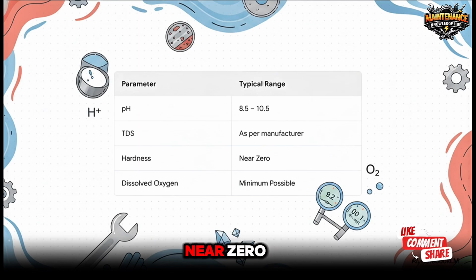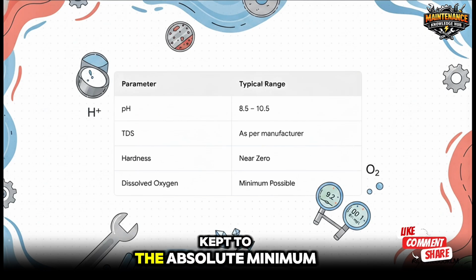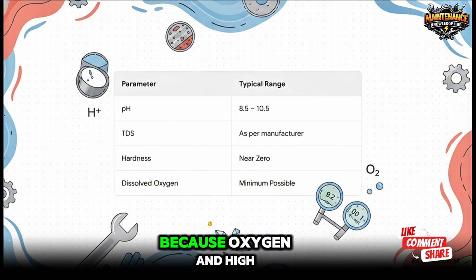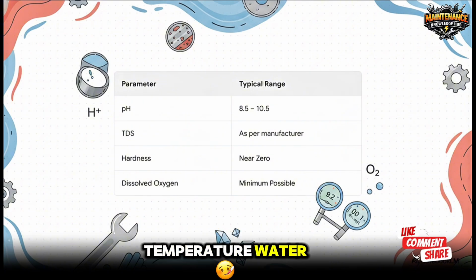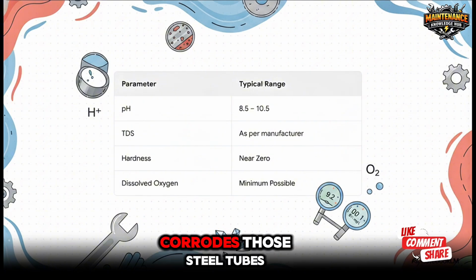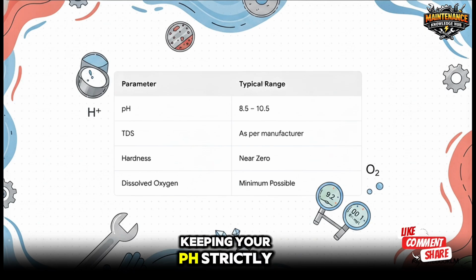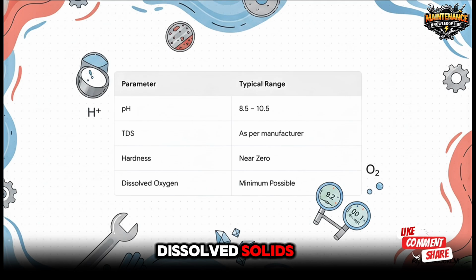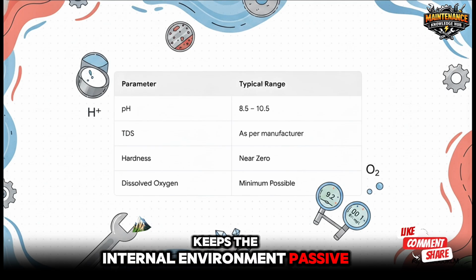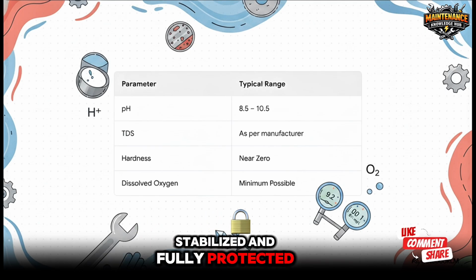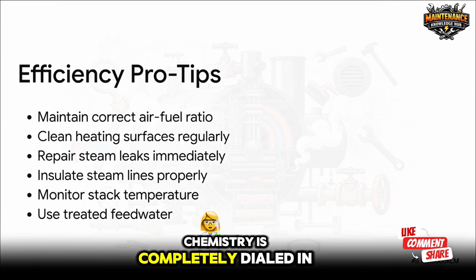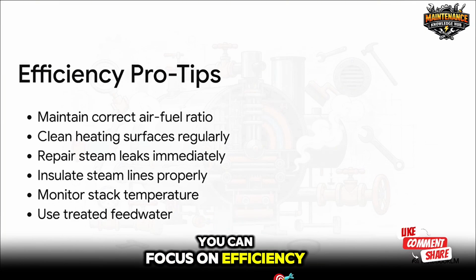Hardness needs to be kept near zero. Dissolved oxygen must be kept to the absolute minimum possible. Why? Because oxygen and high-temperature water actively and rapidly pits and corrodes those steel tubes. Keeping your pH strictly between 8.5 and 10.5 and managing your total dissolved solids keeps the internal environment passive, stabilized, and fully protected. And hey, once your chemistry is completely dialed in, you can focus on efficiency.